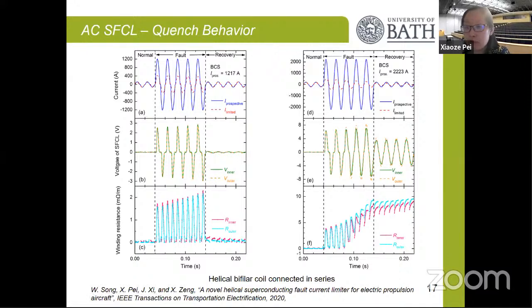And then because the temperature is still pretty high when the fault is cleared, in this case the superconducting fault current limiter is not able to recover. It still has a high resistance even after the fault is cleared, and it would probably struggle to recover under the loaded condition or take longer to recover. So we do need to pay attention to how long the recovery time is. In grid applications, it normally requires, for example, between 1 second and 3 seconds for the recovery.